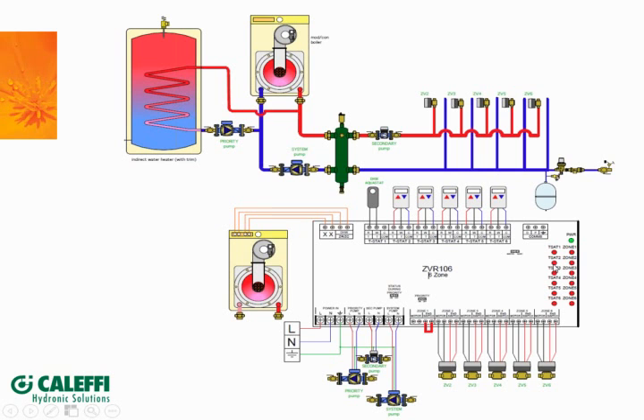And in this case, we're using a priority pump, so we do have to put a jumper in the end switch. But the call for heat LED will illuminate, number 1. And the end switch light will immediately light up because the jumper's in there. So it'll shut down your secondary pump. And in this case, it would also shut down your system pump because we would want this off. And it will fire your priority pump. It will also close the domestic hot water contacts, so the boiler goes to high fire. So we'll load up that indirect. And once it's done, it'll pop back over to normal heating mode.